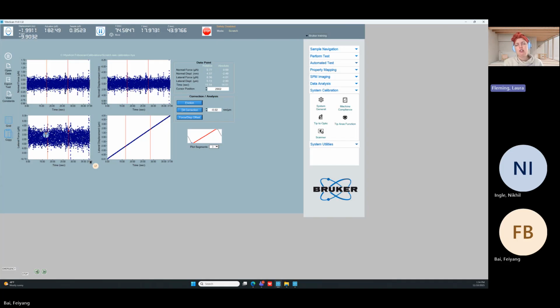It's really hard. Anti-vibration systems are difficult to design, and once you start stacking them, it can become even more difficult. Anti-vibration systems, airtables, don't just dampen everything from 0 hertz up. There is usually a peak. They typically amplify below whatever their peak is, and then they dampen after that. How well they dampen after that depends completely on the anti-vibration system you get. So you can add one, but whether or not it will help is difficult to say. I have seen people successfully add active anti-vibration to these systems, just a little unit that goes around it and sits on. Those I haven't seen a problem with.